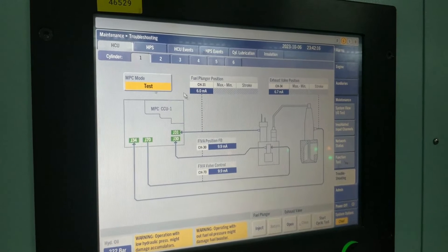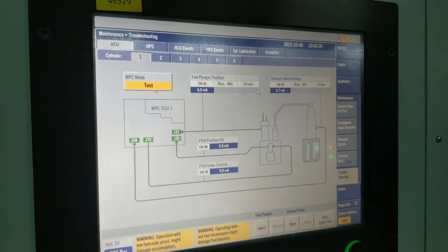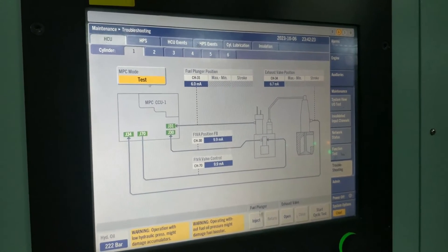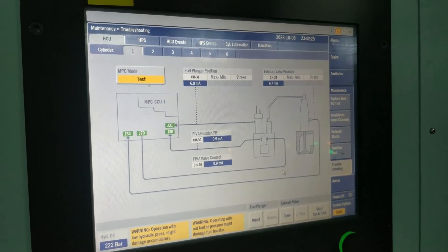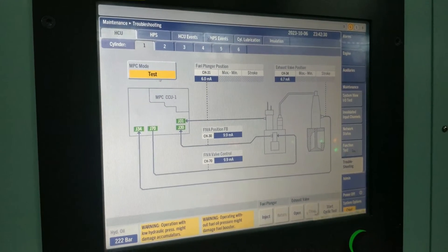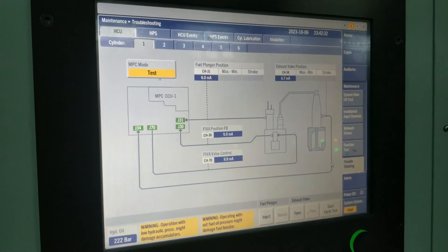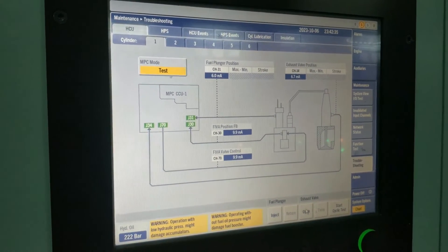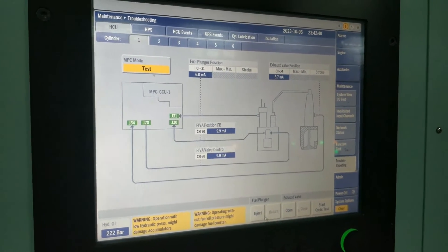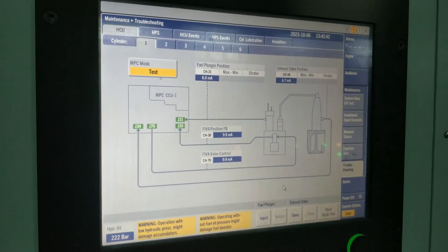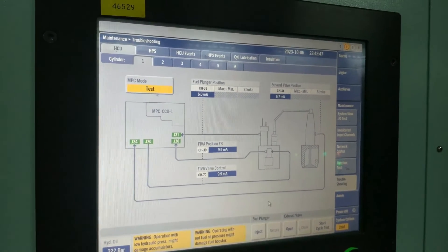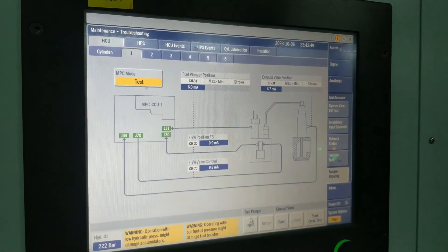If you want to do testing for the fuel injector, you can click this. You can also give the command of open and close manually. If you give cyclic, it will automatically open and close. But if you want to manually open and manually close, that option is also there. Regarding the fuel valve, if you want to inject fuel to the cylinder manually and see whether the fuel valve is working properly or not, you can give this command also.